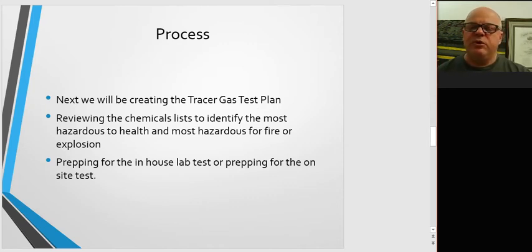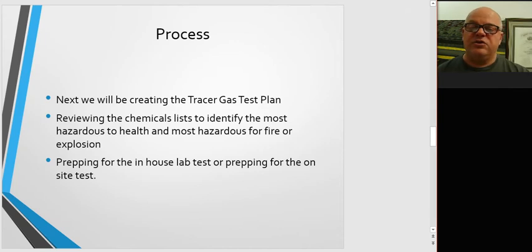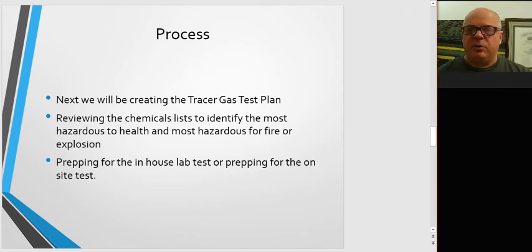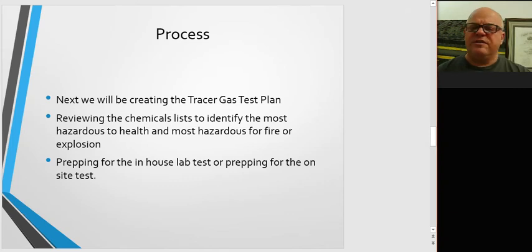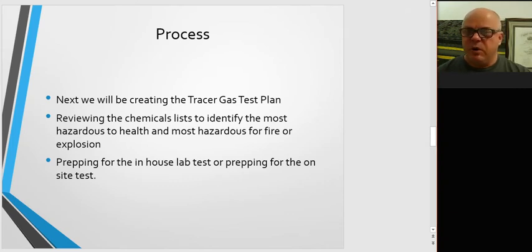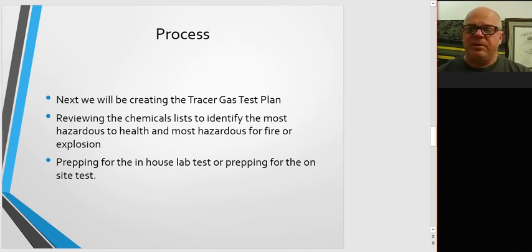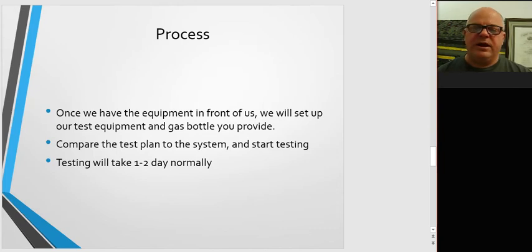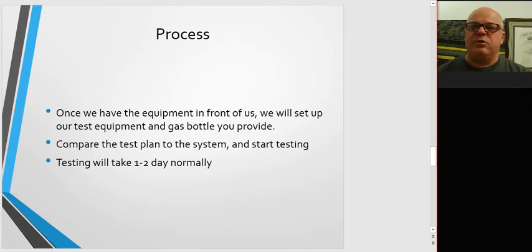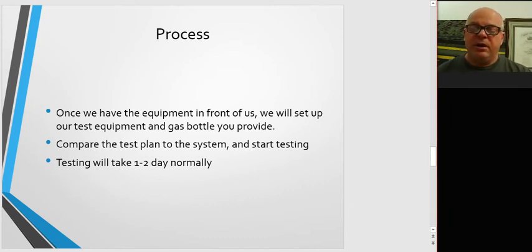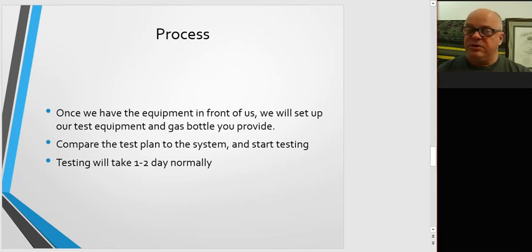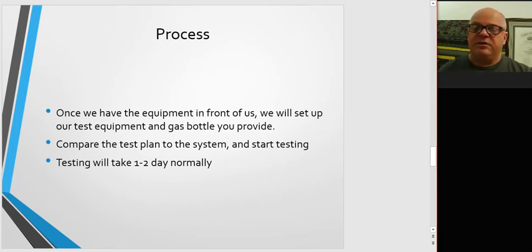Then we'll review the chemical list also in the background, making sure we know which chemicals to test for, their flow rates, and their lower explosive limits and occupational exposure limits. Then we'll be prepping the equipment to come on out and do it there, or we'll be clearing a space here for your equipment to come in. Once we have the equipment in front of us, we'll set up our test equipment and the gas bottle you provide. We'll compare the test plan to the system and meet with you to make sure that's right, and then we'll start testing.